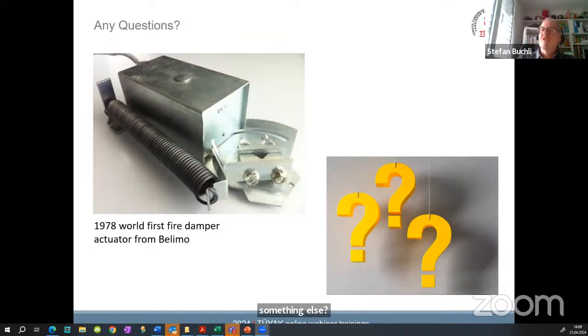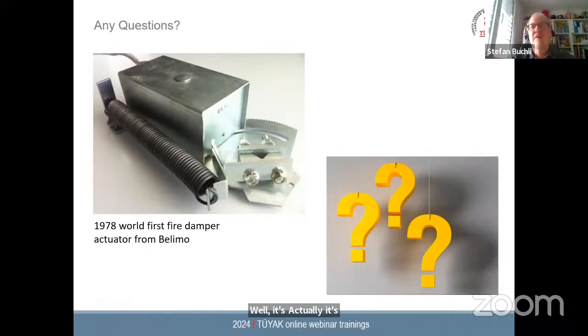Well, what's in the standard that's maybe interesting when you talk about spring return: you always talk about spring return when we talk about one safety position, so the fire damper. The standard itself doesn't say it needs to be a spring. It could, for example, also be another solution like a supercap, which is like an electronic battery storing energy and controlling a standard damper into the closed position. That would also be allowed, but up to now there are no such solutions on the market. But the spring is really a very proven solution. It's a mechanical thing, but it shows something very important: a standard or a regulation should never dictate a technical solution.